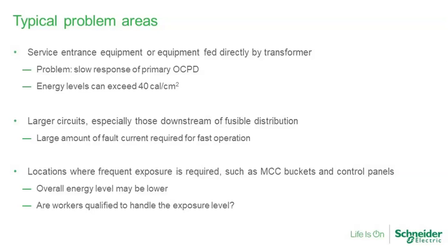That's one of the reasons that the NEC has those requirements in for breakers and fuses 1,200 amps or larger. There may be large amounts of fault current required for fast operation of those devices, and it can result in high energy exposure that way.